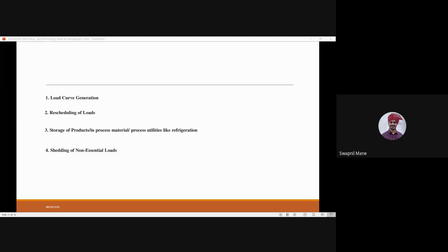Now I will fill up the 5th floor tank, and if there is no requirement of water on the top floors, I will not pump the water. If there is no requirement on the 5 floors below, then water will be stored at the 5th floor, and it will require less power to pump from the 5th floor to the terrace. This sensing will be done by the maximum demand controller.